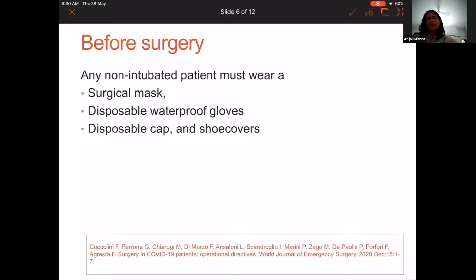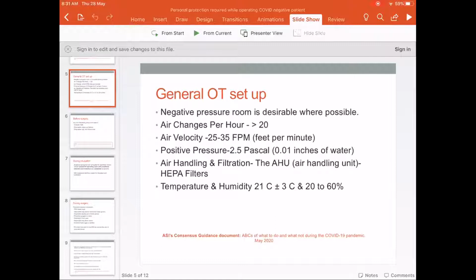Okay. So this is the general OT setup I was talking about. All OTs should have a separate air handling unit, and they should have HEPA filters, that is, high efficiency particulate air filters, which have 99.9% efficiency in filtering particles between 0.1 to 0.3 microns. The temperature and humidity of the operation theater should be 21 degrees plus or minus 3 degrees, and the humidity should be between 20 to 60%.